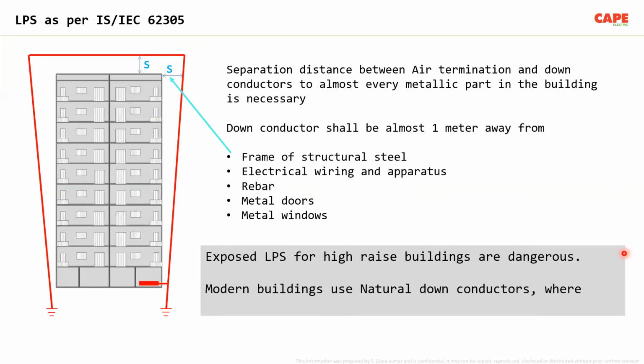Now, what do we do? Exposed LPS for high-rise buildings are dangerous. In a large building, let us say a 20-floor building, do you think you can keep an air terminal 1 meter away from the building? That is really impossible. You cannot do this. So the recommended way in the standard is to use a natural down conductor, meaning use the structural steel as the down conductor.